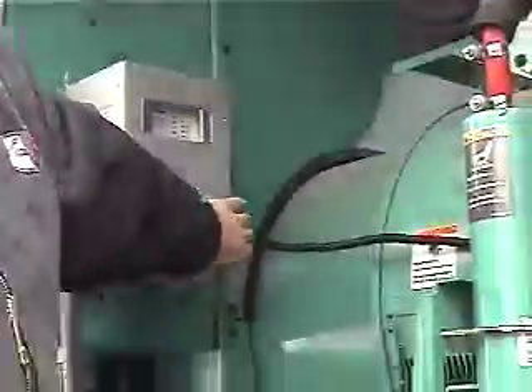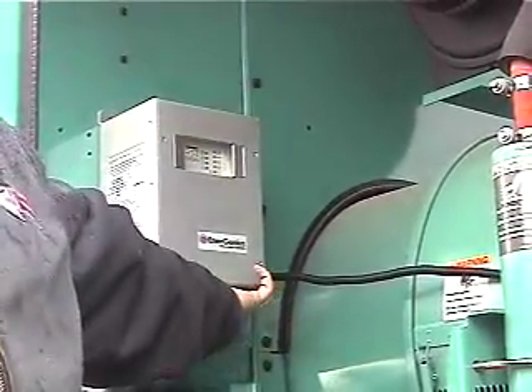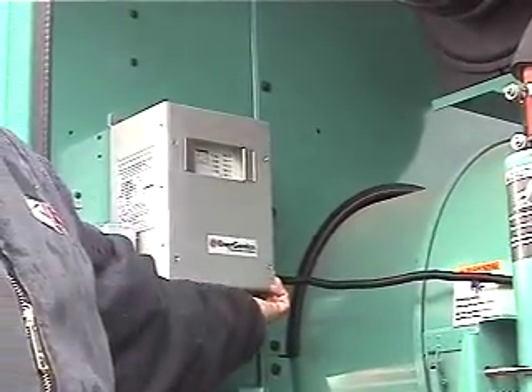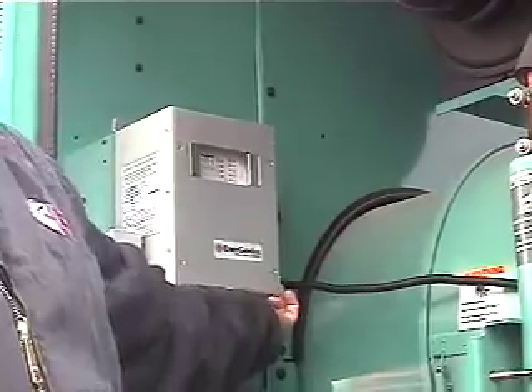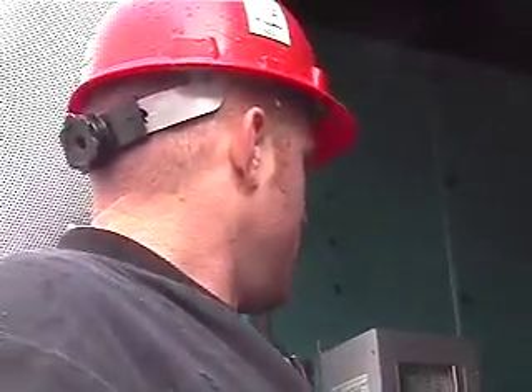Here's your battery charger. Anytime we're not running, batteries need to be charged because we have a lot running off the generator batteries. All of our controls, our annunciator, those are all running off the generator batteries. So this is something you can just tell at a quick glance what it's charging at, what its rate is, how many amps it's charging at. It's a float style charger, so it will turn off when it doesn't need to be on.